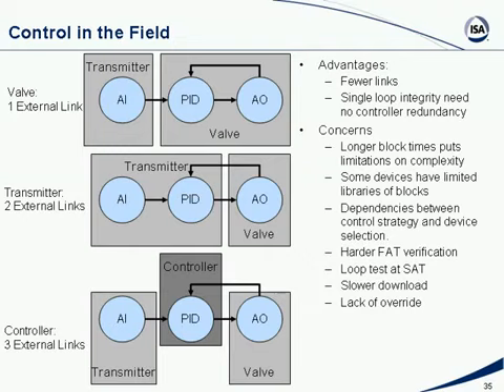This holds true for simple control strategies. If I get a really funky control strategy, including a lot of function blocks, then it becomes better to do it in the centralized controller. Also, if I have interlocks involving other buses, such as Profibus or discrete hardware, then again it makes sense to do it in the controller. So you will find that maybe 20% of your loops remain in the centralized controller and about 80% of the loops go into the field.